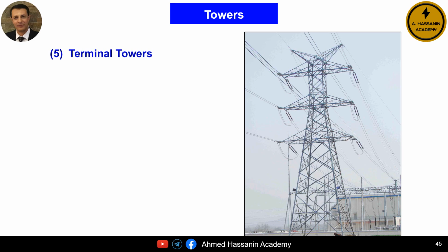Purpose: their main job is to terminate the transmission line. They provide strong mechanical support to handle the full tension of the conductors, since there is no continuation of the line in one direction. They also allow for easy connection to substations or switching stations.